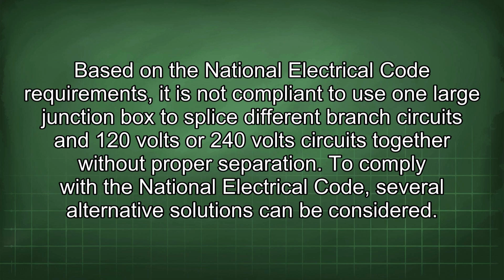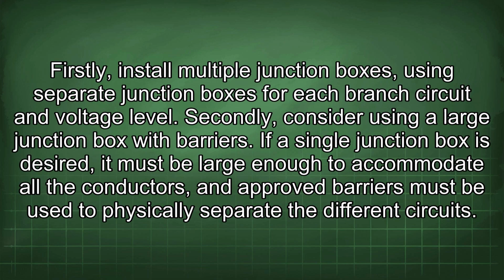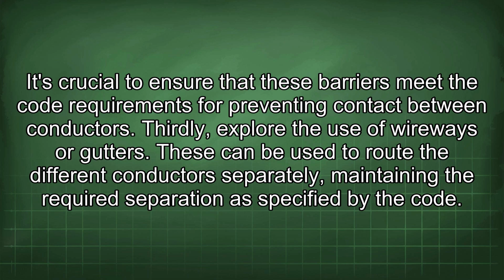To comply with the National Electrical Code, several alternative solutions can be considered. Firstly, install multiple junction boxes, using separate junction boxes for each branch circuit and voltage level. Secondly, consider using a large junction box with barriers. If a single junction box is desired, it must be large enough to accommodate all the conductors, and approved barriers must be used to physically separate the different circuits. It's crucial to ensure that these barriers meet the code requirements for preventing contact between conductors.